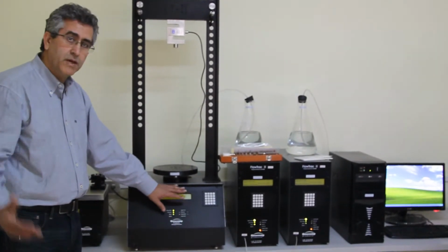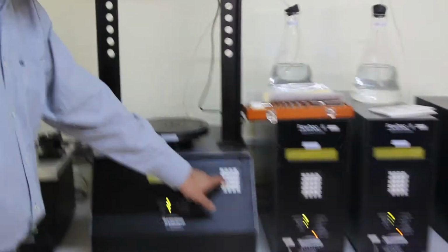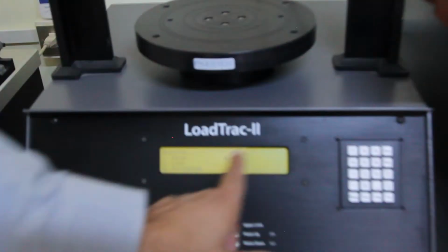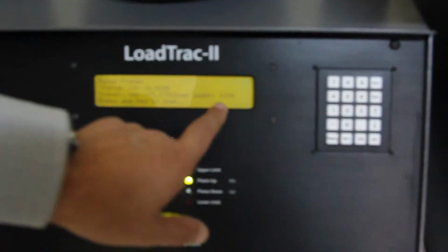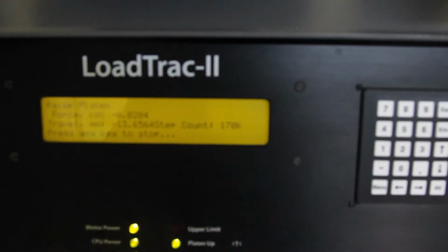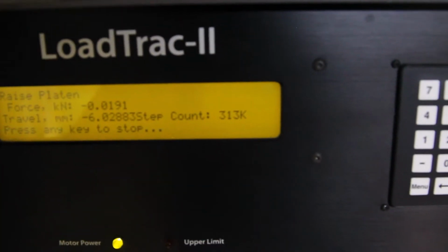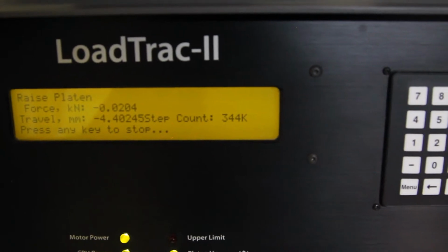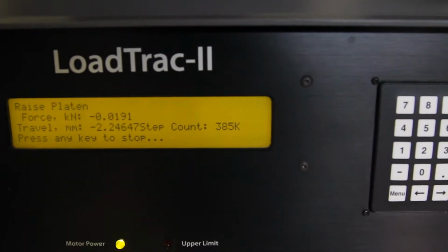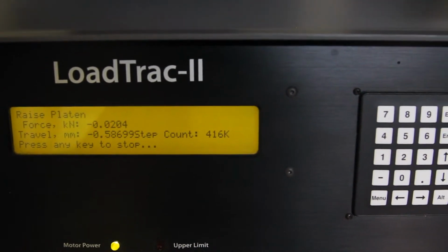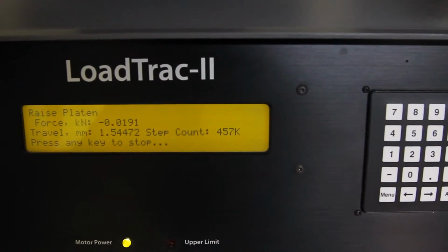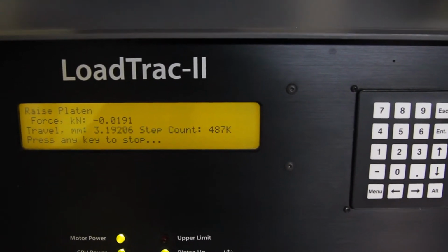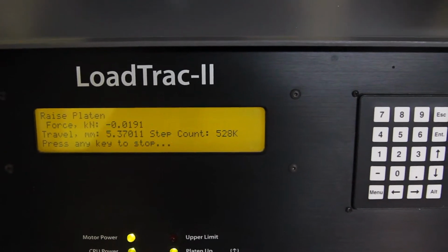So what we're going to do, we're going to go to the menu, and in the menu we're going to go to position, which is number 2, and in this case we're going to raise the platen, and we're going to look at the counts on the far right side, and we want to be about 800 to 900K. Don't pay attention to the readings here because we are doing the calibration now. So we're going to wait until the platen is about halfway, as I said before, and that will correspond to about 800 to 900K. That also will give us a lot of room to insert our gauge blocks underneath the platen so we can do our calibration.